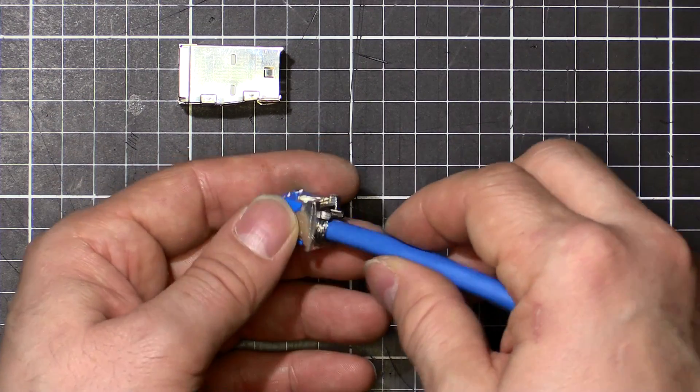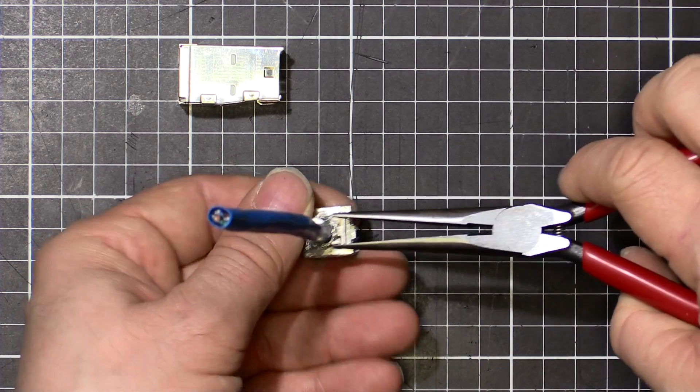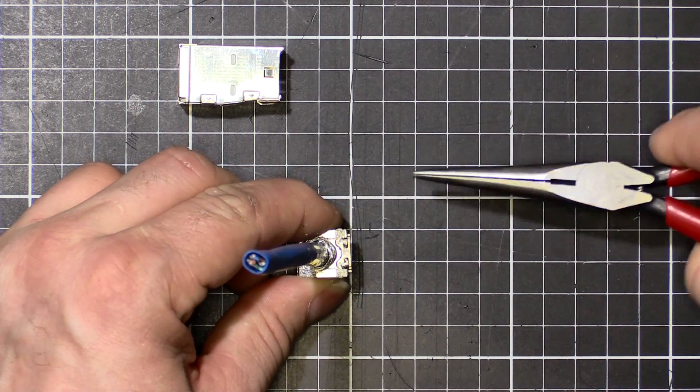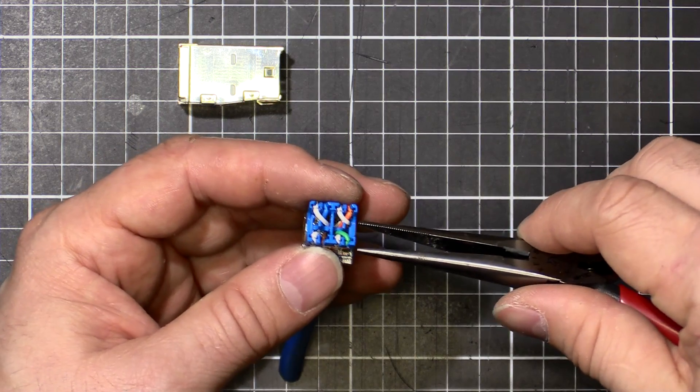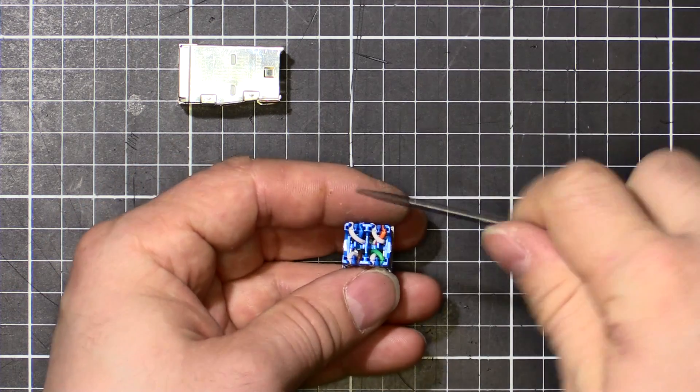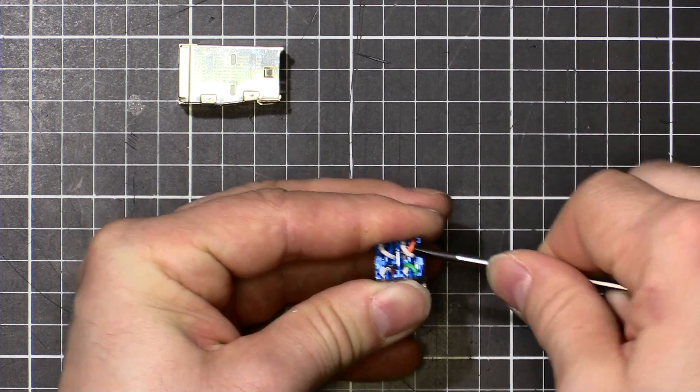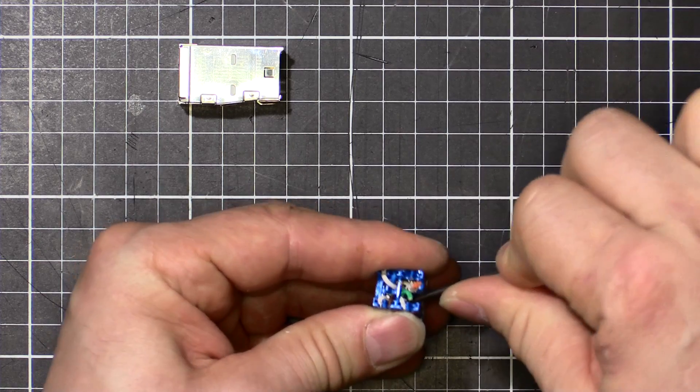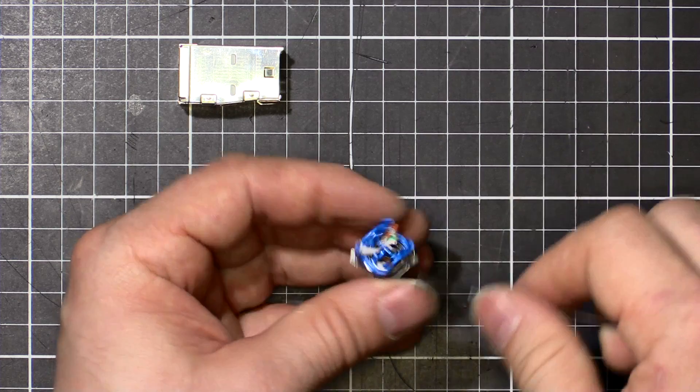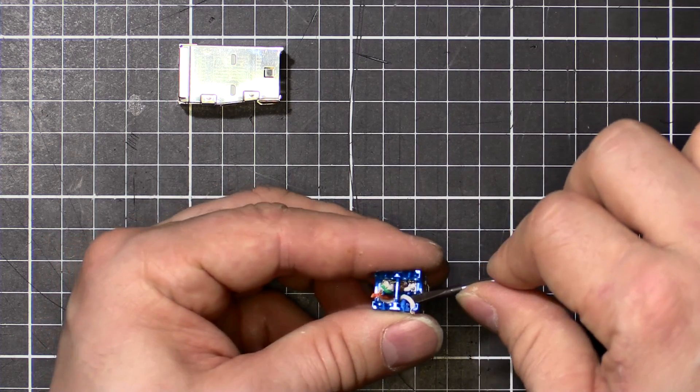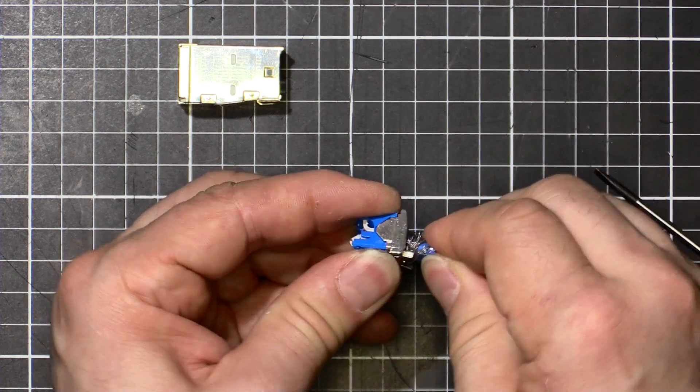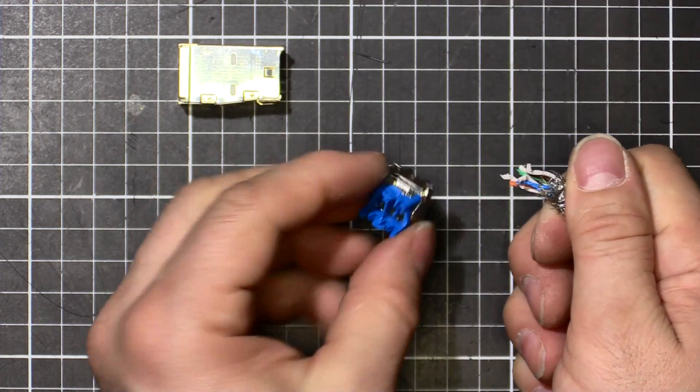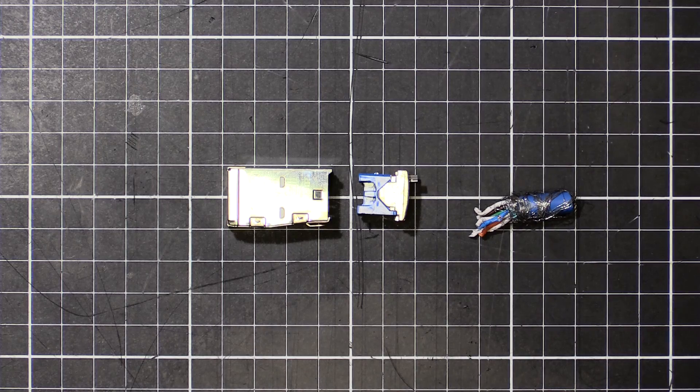And to get the wire out of here, we have to just loosen off our strain relief. Really carefully with your pliers. You can either use your pliers like I said before at the start, in here, or I'll chop this off to get it out of the way. Or you just get in there with your flat blade and lift those up. Because they're not actually tied in there, they're just looped through those little barbs. So if you pull them out, directly inwards, don't lift them up, otherwise you can break the barbs. And then it's a matter of just pulling out. And there we go, ready for reuse. No worries.